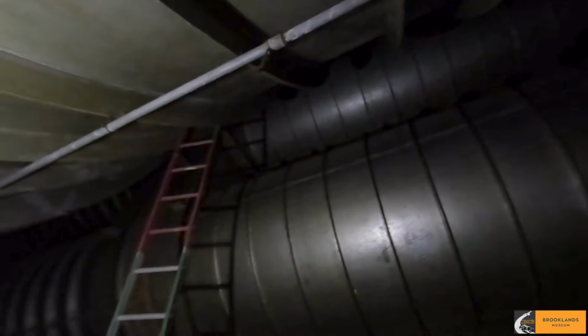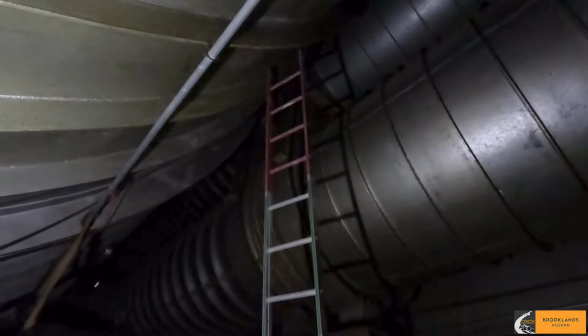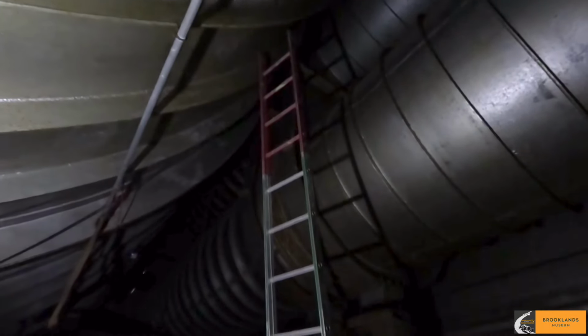And as you look into the middle of these ducts, you can see the expansion joints that were in there, because, as we've said, you can get down to minus 65 Celsius, but also you could get up to 50 Celsius underneath here. So that's over 100 degrees. So there's quite a bit of expansion. So you need a little bit of an expansion joint, shall we say, to allow things to move. Similarly, the pipework on here, if you look to the left of it, you can see what are known as swan necks, which again are to do with the expansion to allow for 100 degrees difference.